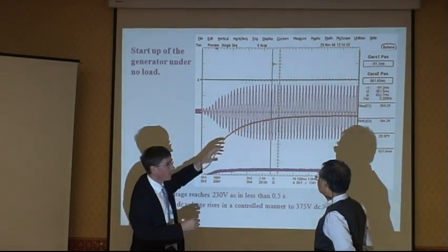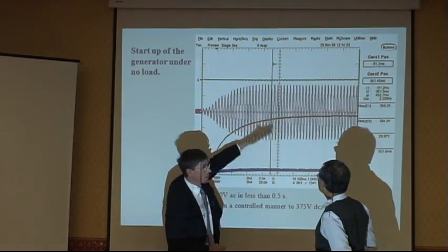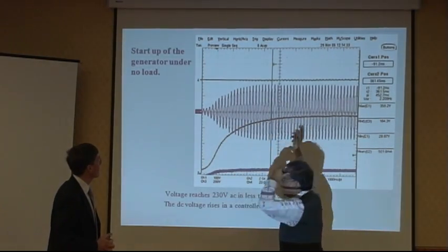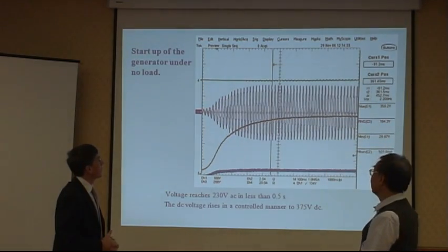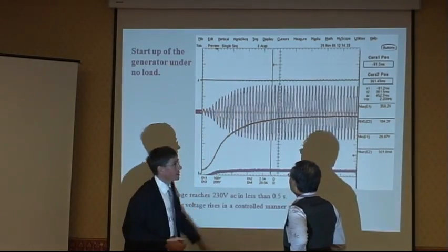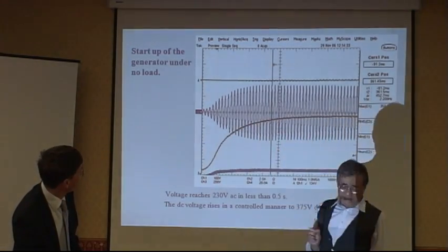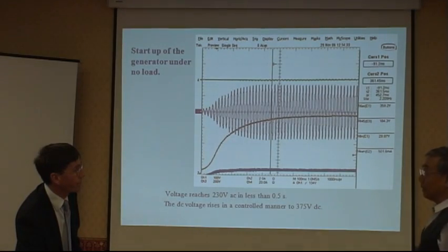So this is the DC supply between the generator and the output inverter. We have DC going up to 400 volts DC. 这个是逐渐的电流，产生的电流再给磁场，越来越高。这是给交流变频器的直流电源，直流电压建立到400伏特。再用它变成230伏特、50赫兹输出。And this is the output voltage, 50 Hz, rises to 230 volts RMS.